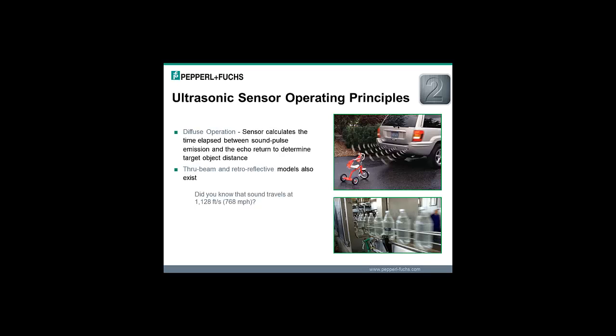Okay, next we're going to discuss the ultrasonic sensor operating principles. The first and probably most popular mode is diffused operation. In this mode, the sensor calculates the time elapsed from when it emits a sound pulse and when the echo pulse returns, and it uses the speed of sound to do that. It knows that the speed of sound travels at 1,128 feet per second. So by sending out a pulse and calculating the time it took for that pulse to come back, it can tell how close or far away something is.